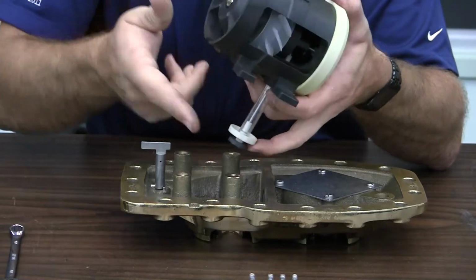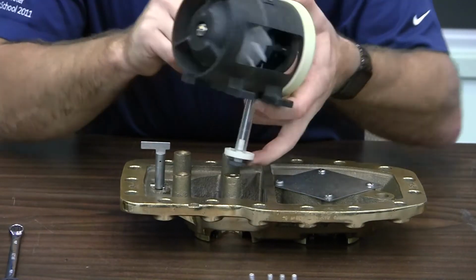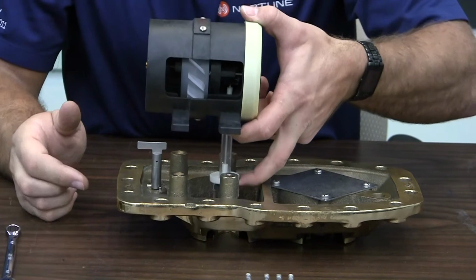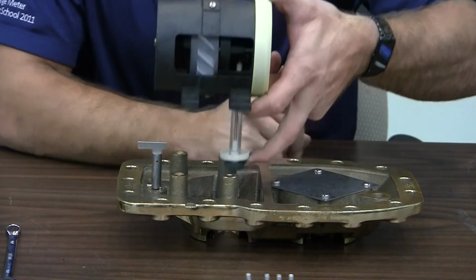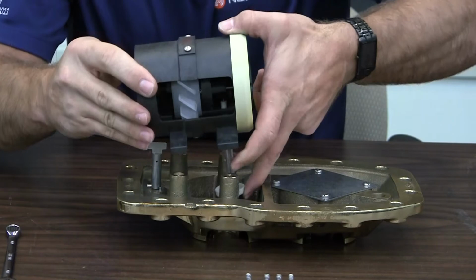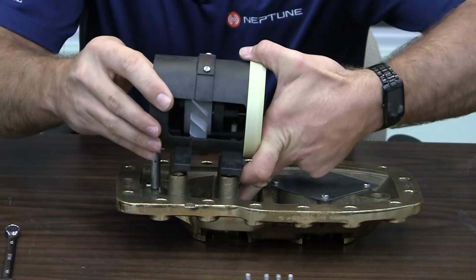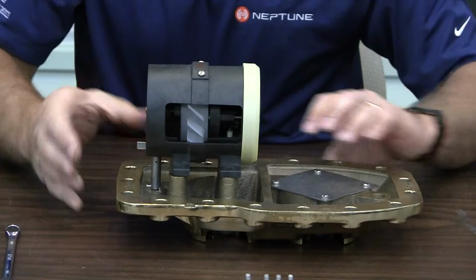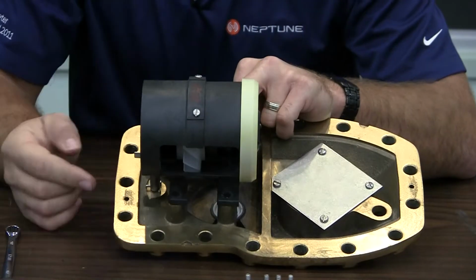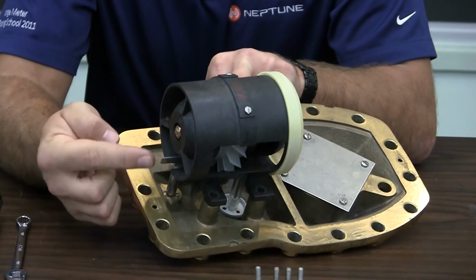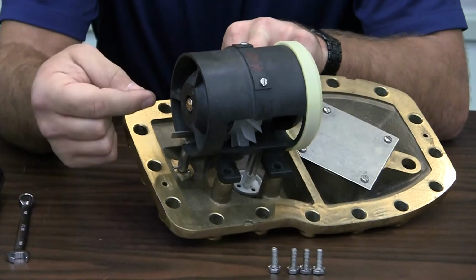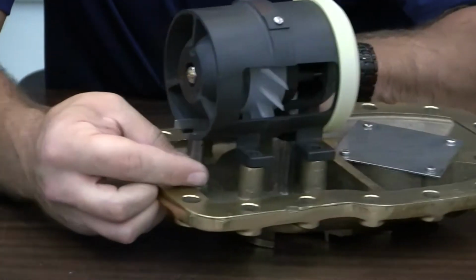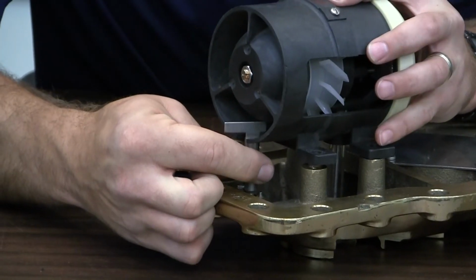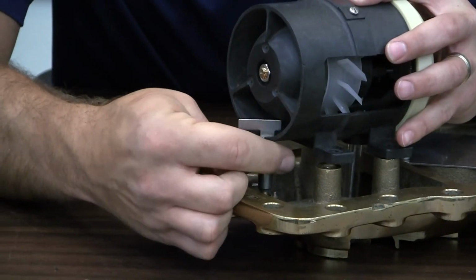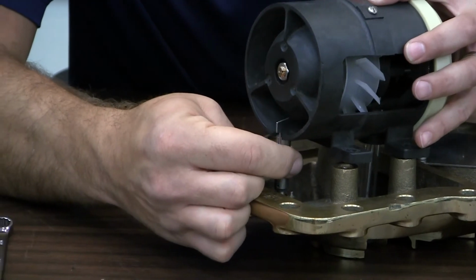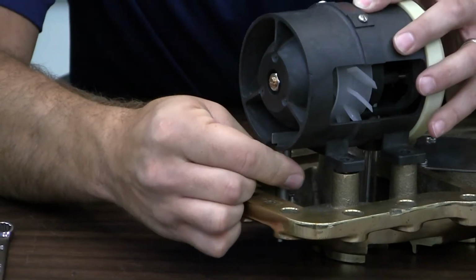While taking your finger and holding the bottom of the magnet drive, facing the seal to the main valve towards the chamber side of the cover, you'll place the turbine back in. So sliding that down. Once you line that up, the feet of the turbine should sit on the cover. But if you remember, we've moved the calibration vane to leave the long side out. We'll have to put the calibration vane back in place, and you'll do so just by slightly lifting up on the turbine and on the calibration vane so that it's back in place.